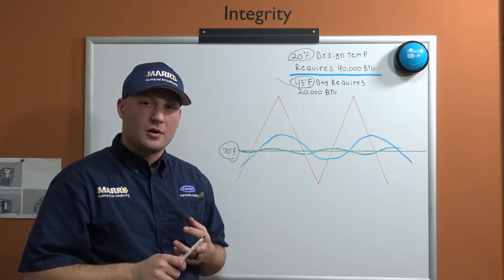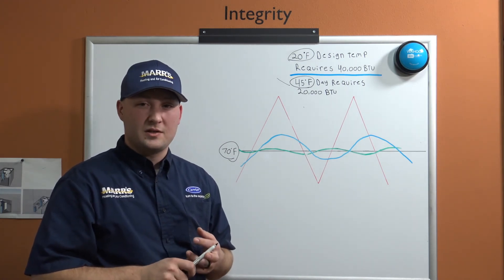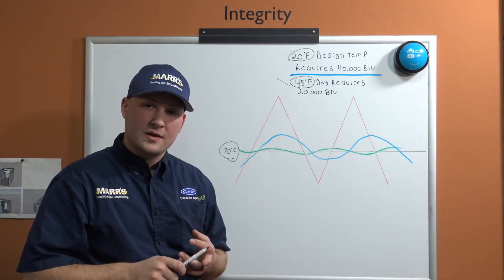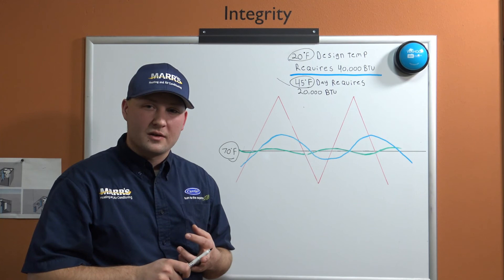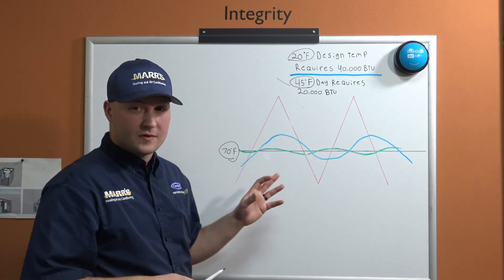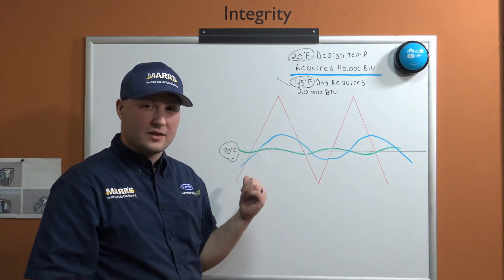What that means is longer run times, and because we have longer run times, our fan is running more. Our fan is variable speed too, so we're running at lower speed, which means less noise. We're filtering more air because we're moving more air in the house. Our outdoor equipment on these systems are a lot quieter than your typical two-stage and single-stage equipment. They're also more efficient.